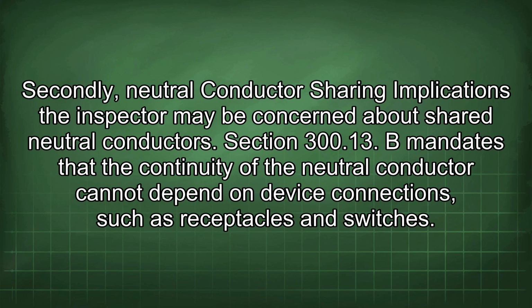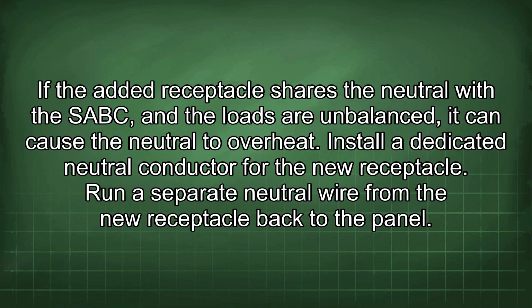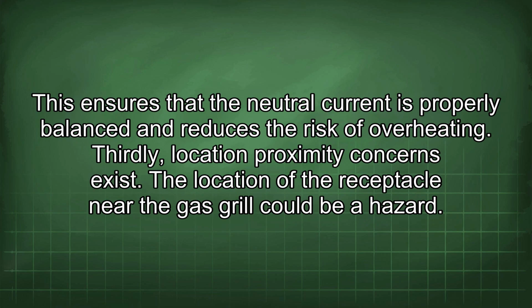Secondly, neutral conductor sharing implications. The inspector may be concerned about shared neutral conductors. Section 300.13(B) mandates that the continuity of the neutral conductor cannot depend on device connections such as receptacles and switches. If the added receptacle shares the neutral with the SABC and the loads are unbalanced, it can cause the neutral to overheat. Install a dedicated neutral conductor for the new receptacle. Run a separate neutral wire from the new receptacle back to the panel. This ensures that the neutral current is properly balanced and reduces the risk of overheating.